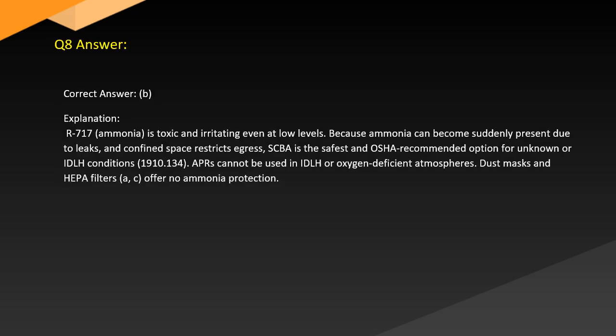Answer. Correct answer. B. Explanation. R717 ammonia is toxic and irritating even at low levels, because ammonia can become suddenly present due to leaks and confined space restricts egress. SCBA is the safest and OSHA-recommended option for unknown or IDLH conditions. 1910.134. APRs cannot be used in IDLH or oxygen-deficient atmospheres. C. Dust masks and HEPA filters offer no ammonia protection.